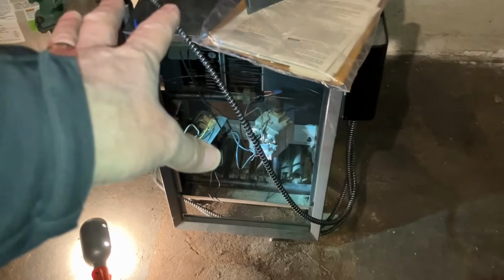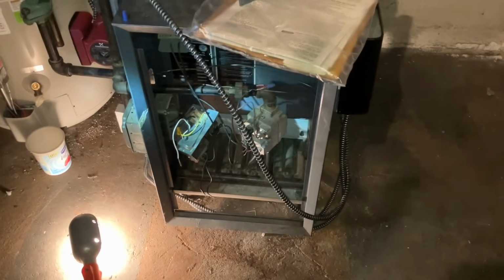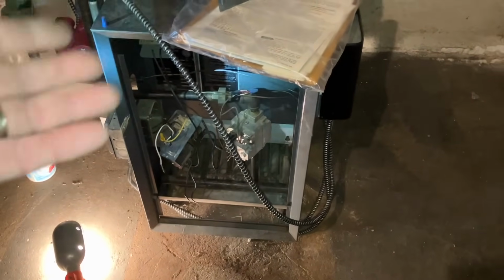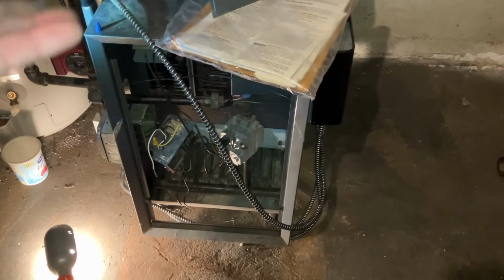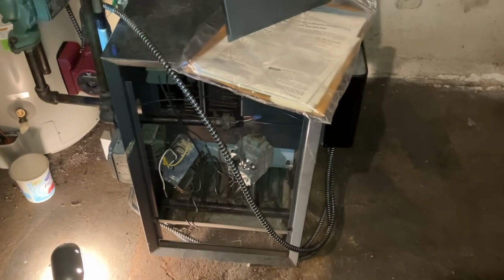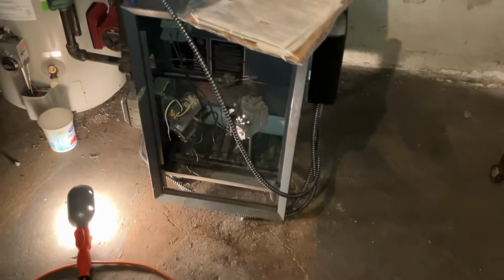Because if you didn't have the high limit, the boiler would run until it's told to turn off, right? But you don't have a steam boiler. You have a domestic, 180-degree cast iron boiler for hydronic purposes. So it's got limits. It'll turn off above 180.